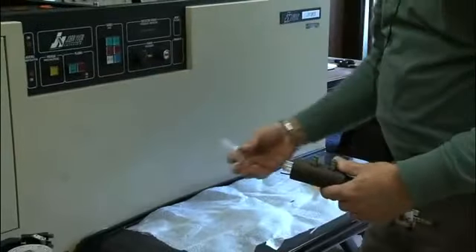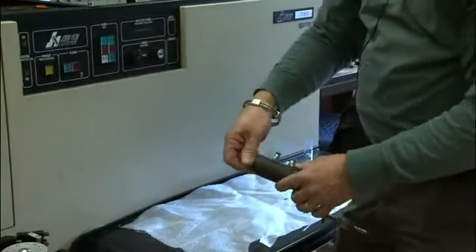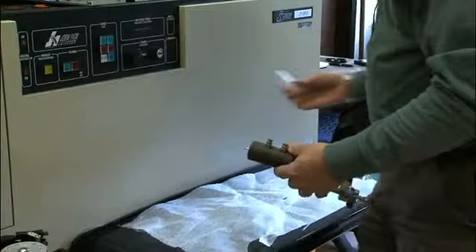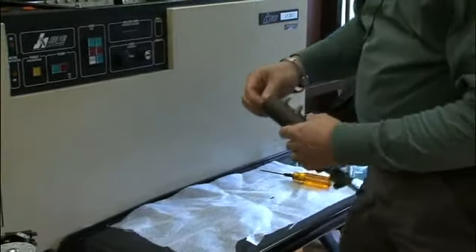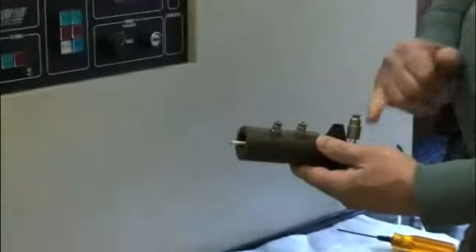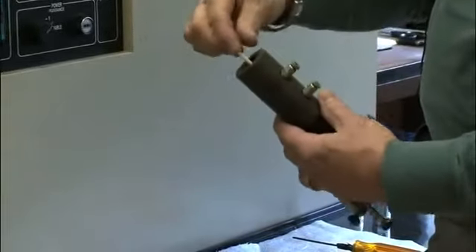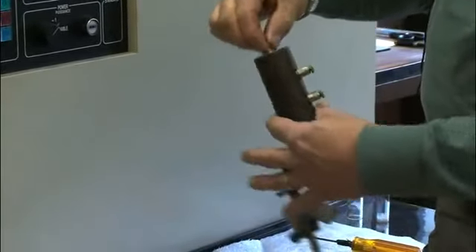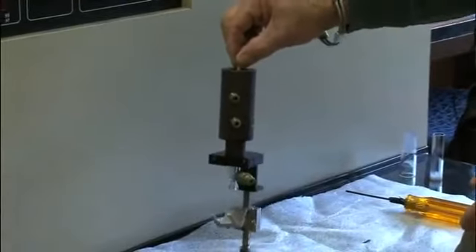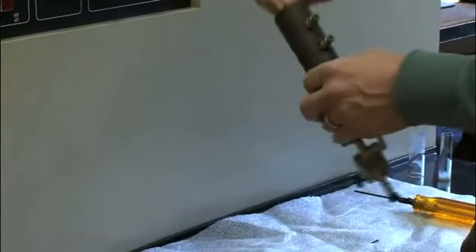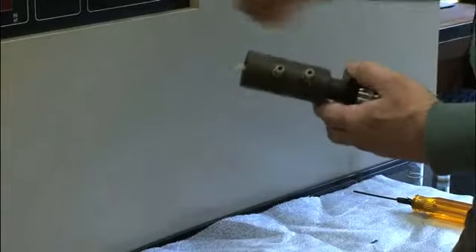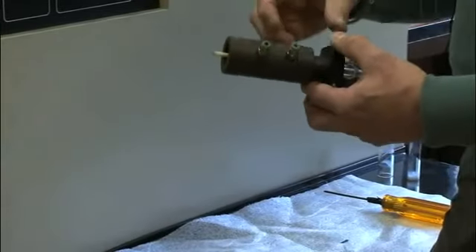So I will take this apart to show you the components. This is called the outer quartz tube. These tubes all slide out. This is the injector, which is where your sample will come into the plasma. If you can hold the torch by the injector and the injector doesn't come out, then your Teflon piece that this plugs into, you know that that's a nice tight fit, and that's what you always want to have.